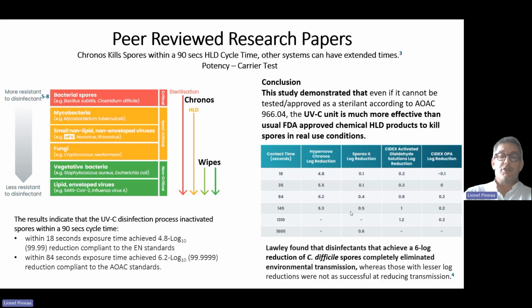According to the study we have published in 2022, we clearly demonstrate that UVC disinfection process inactivated spores within 90 seconds, with a 6.2 log reduction within only 84 seconds. Furthermore, this study clearly indicates that the UVC unit was much more effective than usual FDA-approved chemical high-level disinfectant product to kill spores in real-use conditions. So another time, we demonstrate that UVC disinfection process can achieve the same efficacy level and even more on bacterial spores than already clear chemical disinfectant.